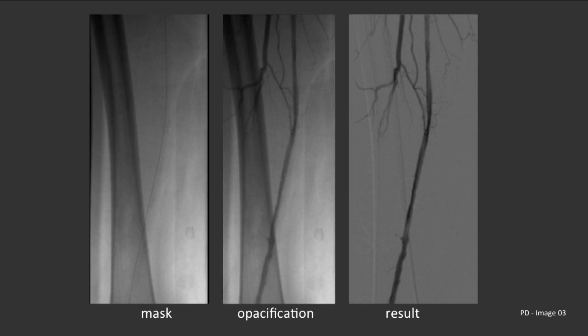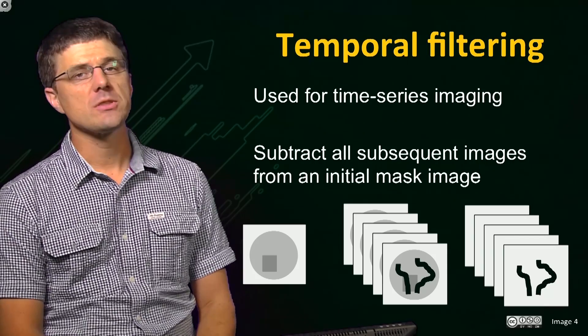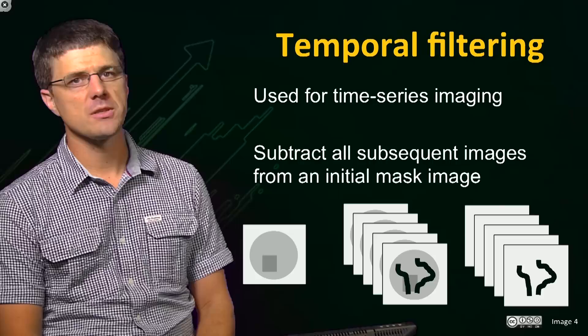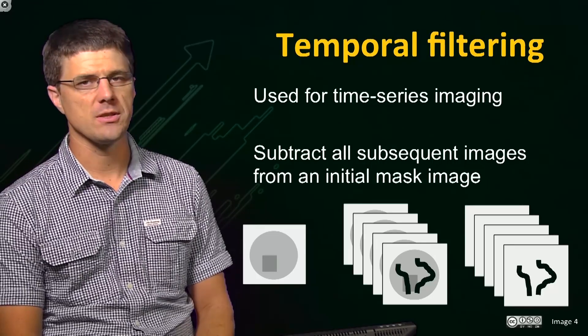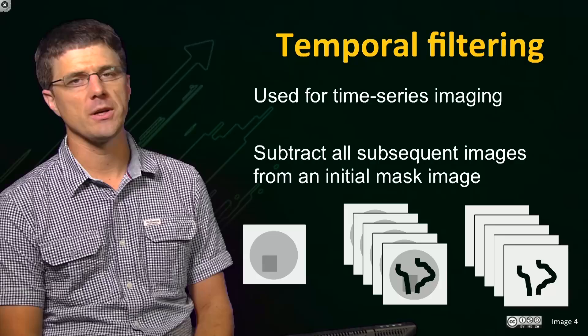In this example we have used a linear subtraction method, as it is easy to demonstrate. In the real world, X-rays penetrate tissues non-linearly, and in order to compensate for this, we would calculate the natural logarithm on a pixel by pixel basis for each of the images before subtraction. This process can then be applied for a time series of images in which each of the subsequent images are processed using the same initial mask image.